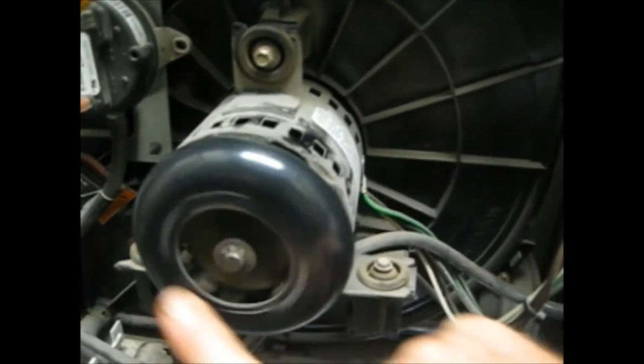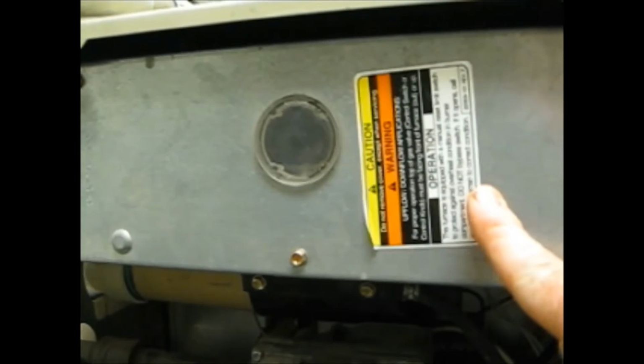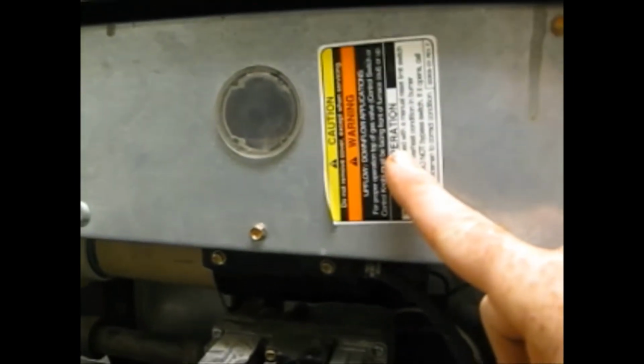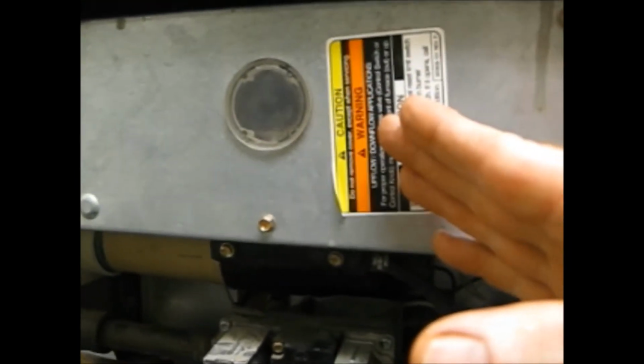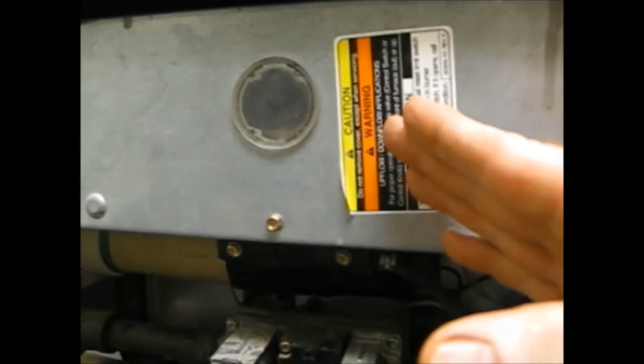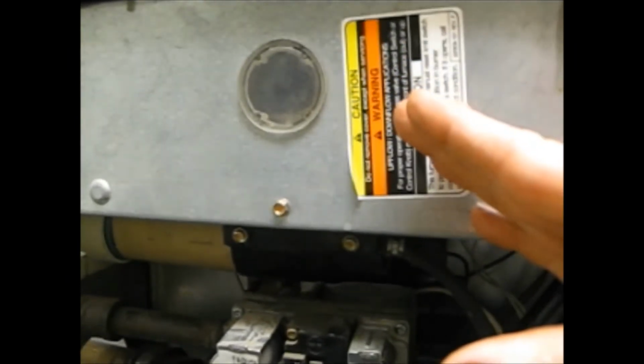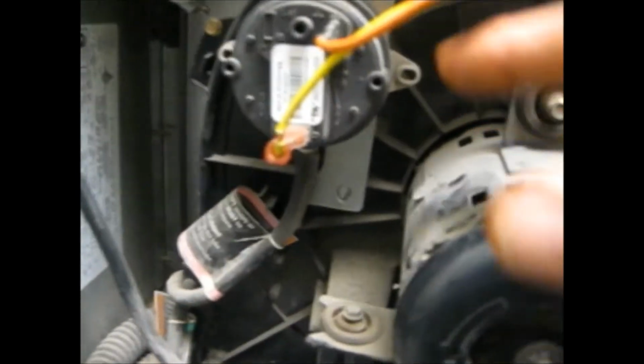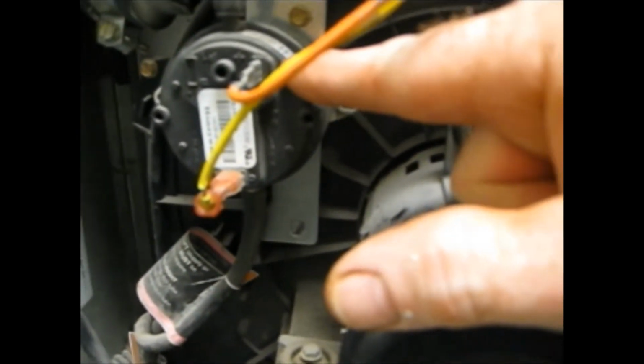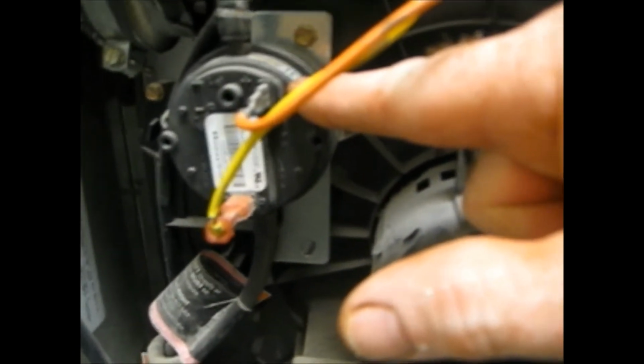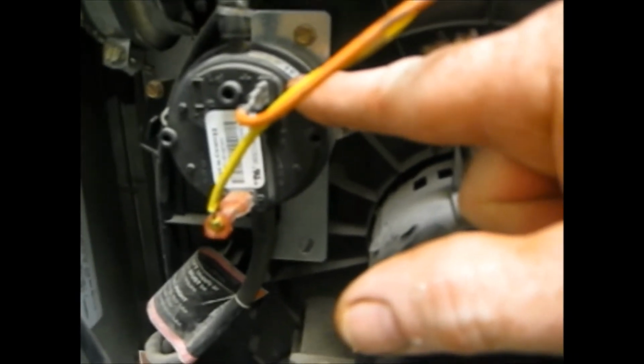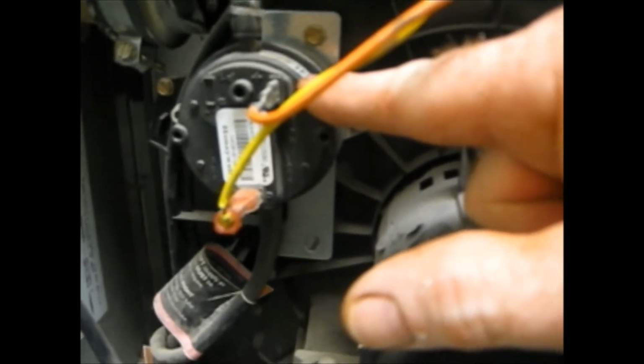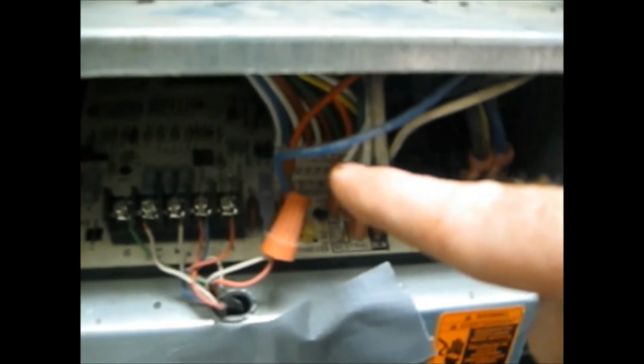This inducer motor will start to spin and will send air up to the burner assembly, and will start purging any gases that could be inside this compartment. As it builds up air pressure, a pressure switch will recognize that there's adequate pressure or air movement up in the burner, and this will send a signal back down here to the circuit board.